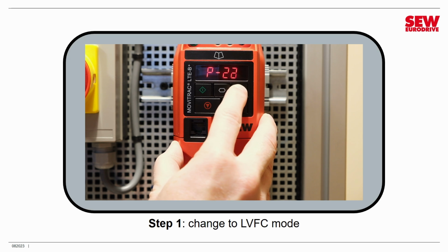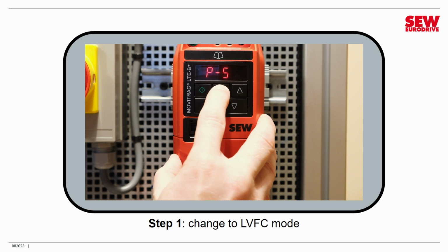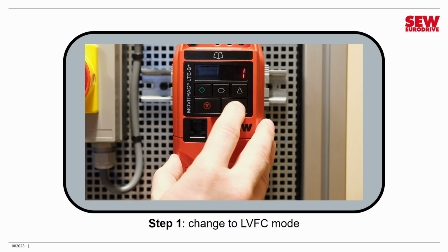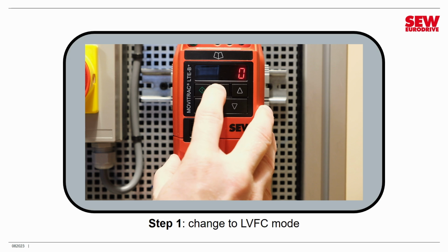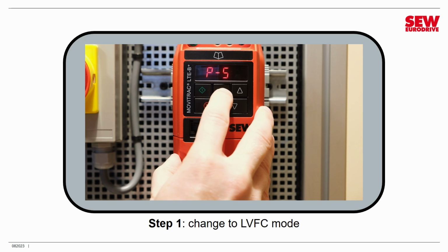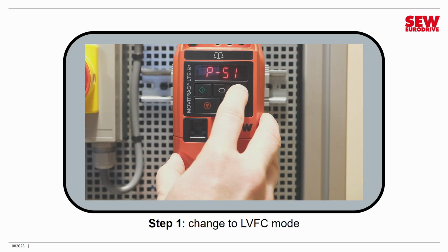You notice now I can go past parameter 14. So I go ahead to parameter 51. And I hit navigate. You can see it's set to 1 right now, which is VF mode. I'm going to change it to 0 and hit navigate again. And that completes changing to LVFC mode.